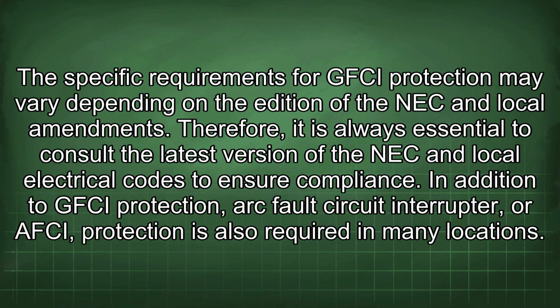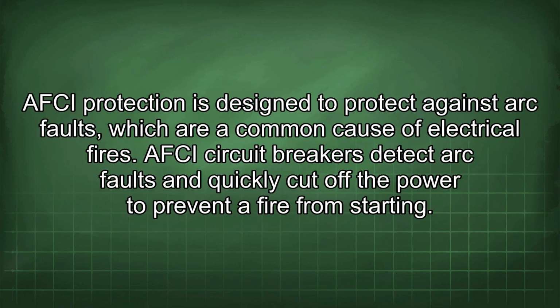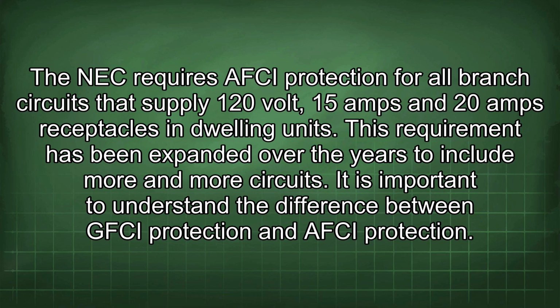The specific requirements for GFCI protection may vary depending on the edition of the NEC and local amendments. Therefore, it is always essential to consult the latest version of the NEC and local electrical codes to ensure compliance. In addition to GFCI protection, arc fault circuit interrupter, or AFCI, protection is also required in many locations. AFCI protection is designed to protect against arc faults, which are a common cause of electrical fires. AFCI circuit breakers detect arc faults and quickly cut off the power to prevent a fire from starting. The NEC requires AFCI protection for all branch circuits that supply 120 volt, 15 amp and 20 amp receptacles in dwelling units. This requirement has been expanded over the years to include more and more circuits.